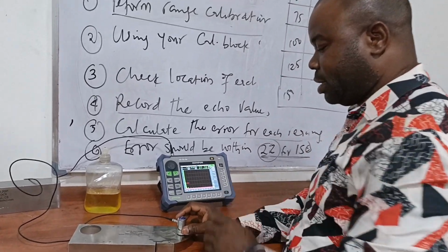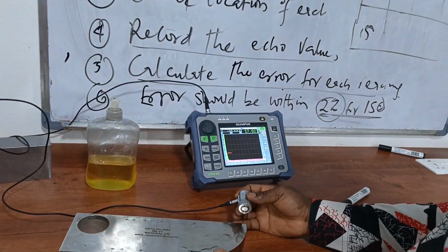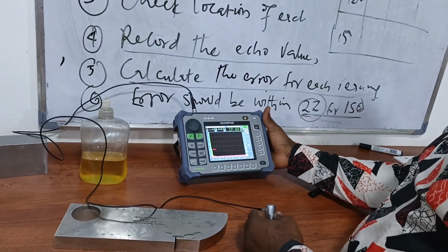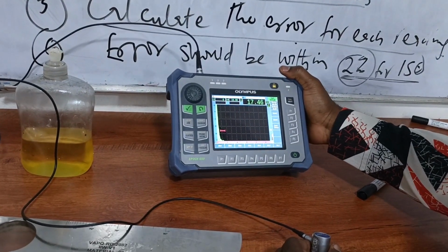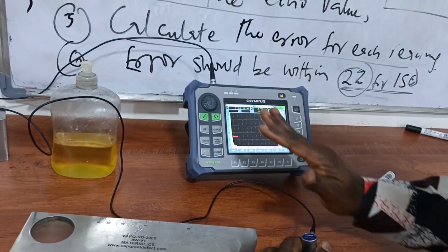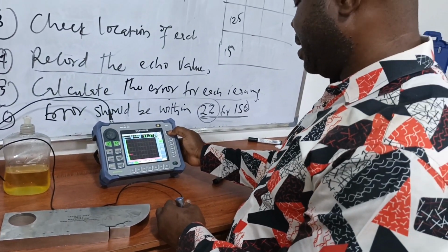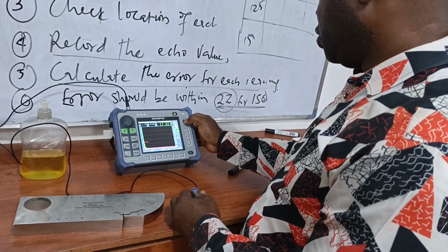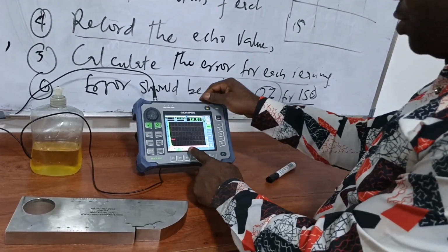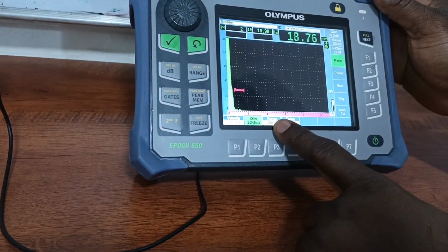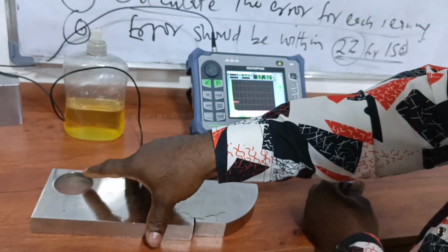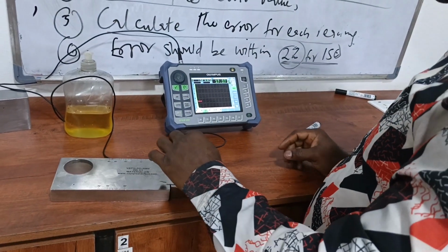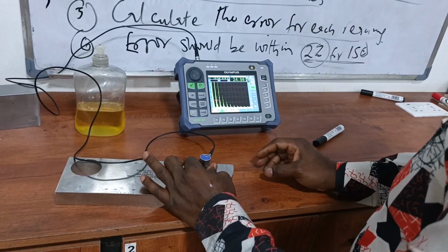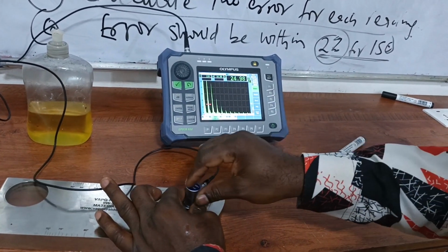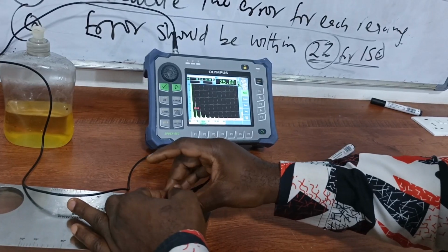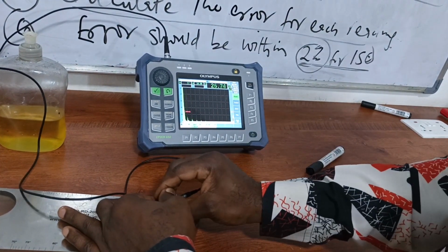Now, let's demonstrate the horizontal linearity. We are using our Olympus Epoch 650. I have set up the equipment, I have done my range calibration, and I have set my equipment range to 250. If you look at the range here, you'll see that my range is 250. Why am I using 250? Because this block is 25 mm and I need 10 echoes. So if I put my probe on the block, if you look at my first reading, I'm getting almost 24.98.